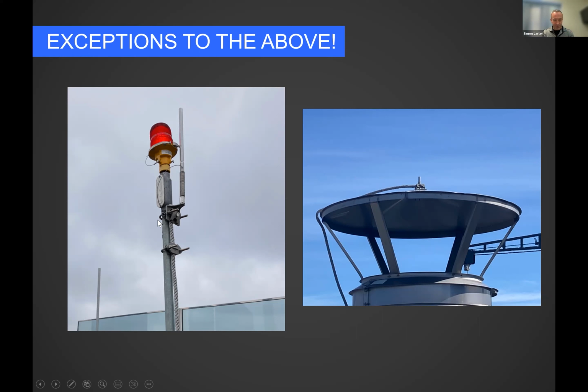The picture on the left is city center down here in Calgary. The picture on the right is on top of the Bow Tower—they just did a huge BME renovation. They would not let us put lightning rods on top of those air units or vents because they would just get knocked over. We said, look, we'll put spring-mounted rods. They said nope, because there wasn't even enough clearance to allow the spring to flex—they had like 2-3 inches of clearance over the tops of those vents. So we had to use a short, stubbier lightning rod as an attachment point. There's nothing else we can do about it—we lost that argument.